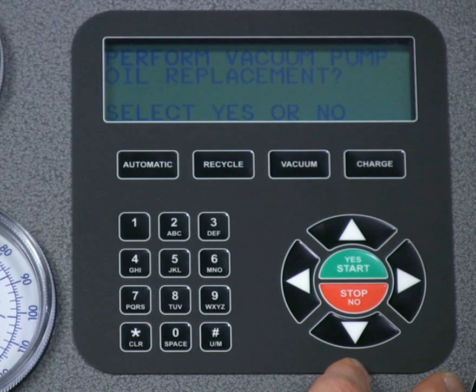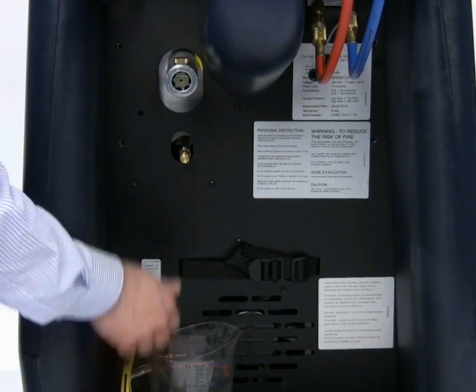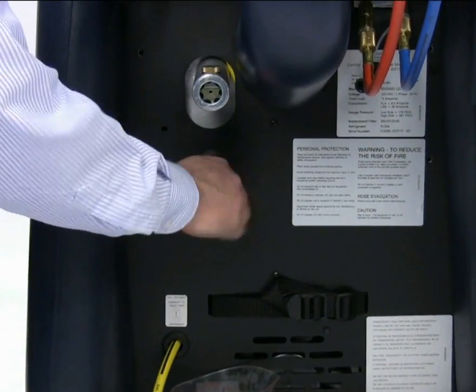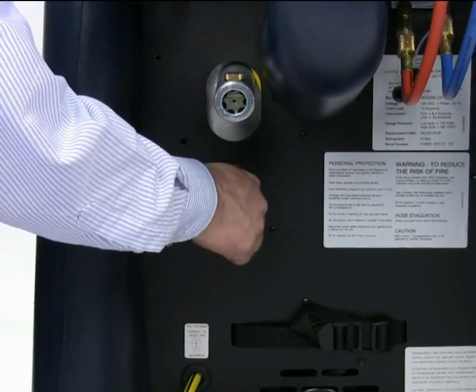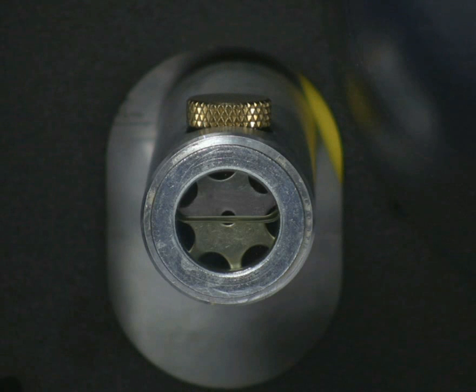RTI recommends vacuum pump oil evaluation after every 10 hours of pump use, and as a reminder, the RHS980 will display an alert every 10 hours of pump use. Separate drain and fill ports for the vacuum pump protrude from the rear wall of the RHS980 on the left side of the machine. A sight glass for viewing the oil level in the vacuum pump is located on the end of the fill port extension tube.